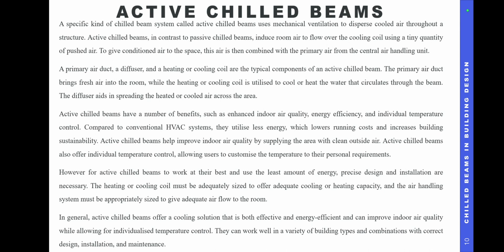However, for active chilled beams to work at their best and use the least amount of energy, precise design and installation are necessary. The heating or cooling coil must be adequately sized to offer adequate cooling or heating capacity, and the air handling system must be appropriately sized to give adequate airflow to the room.